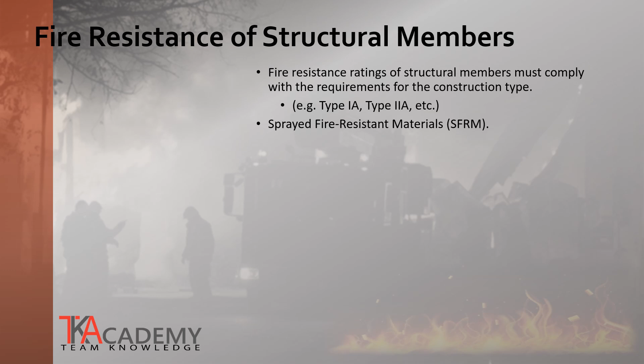When the building's structural framing requires additional protection, it is often done with sprayed fire-resistant material, or SFRM. The fire resistance rating depends upon the minimal thickness, the dry density of the spray material, the application method used, the substrate material, and the spray material's physical properties. This is a tested product that will determine the fire resistance rating that can be applied to the structural system.